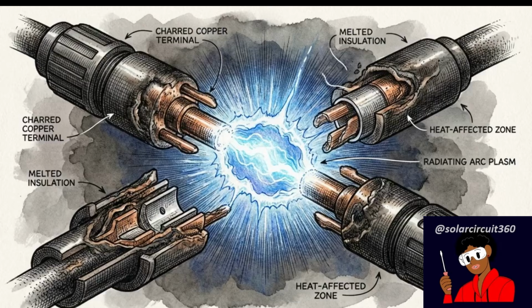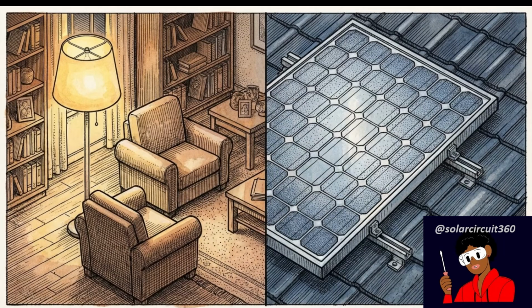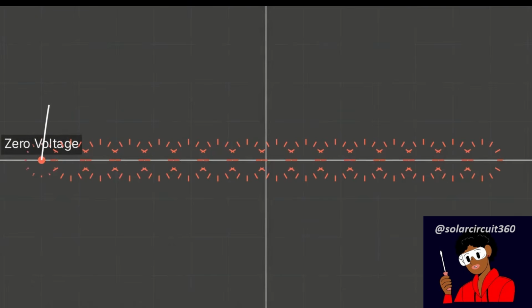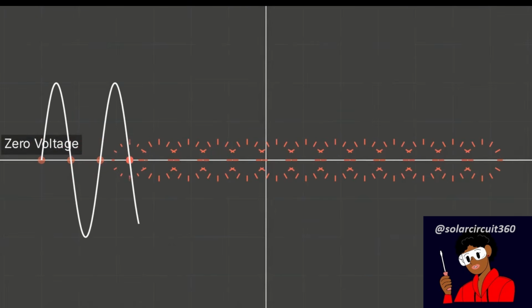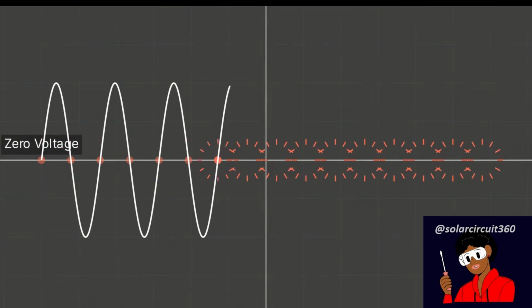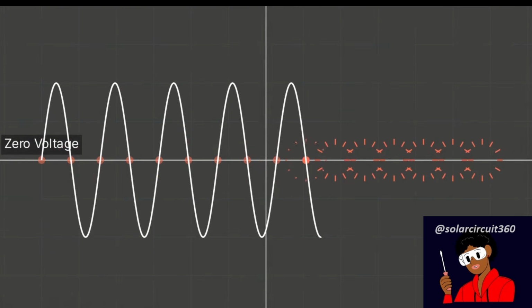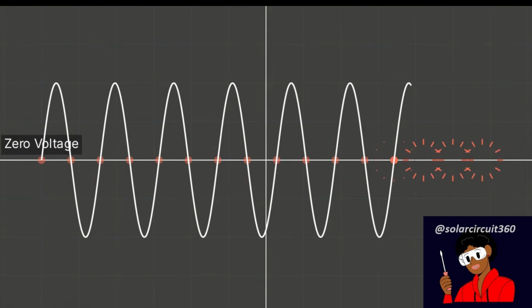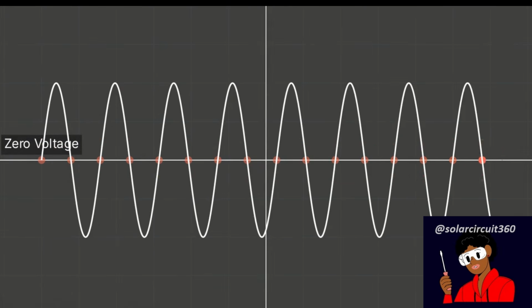Once an arc ignites, the behavior of the electricity dictates what happens next. And there is a critical physical difference between the alternating current in your home and the power generated by a solar array. This chart illustrates alternating current, or AC. The sine wave oscillates up and down, dropping voltage to 0 50 to 60 times per second. That constant zero crossing acts as a built-in off switch, instantly starving the arc.